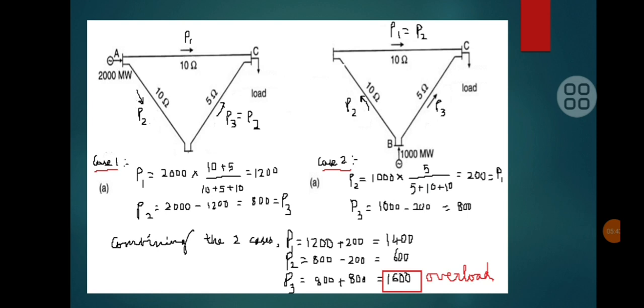The total power in the transmission line AC will be 1400 megawatts. In line AB it is 600, and in line BC it is 1600 megawatts. We have seen that the rating of the line BC is 1250 only, so it is carrying 1600 megawatts here. That means it is overloaded. But the lines AB and AC are normally loaded; they are carrying power less than their ratings. In order to rectify this problem, to remove the overload, we have two solutions. One is to reduce the generation at B and increase the generation at A. That involves the generation operators. Instead of that, the second method is by implementing some changes in the transmission line itself. We can do this.